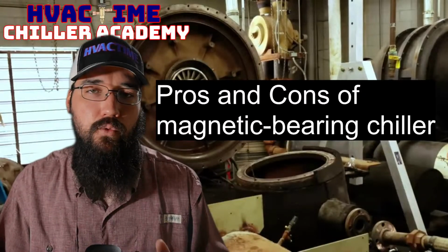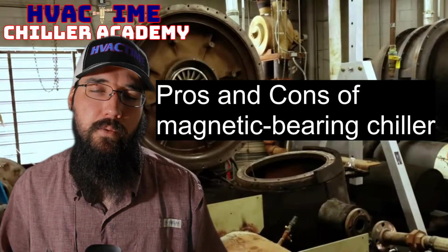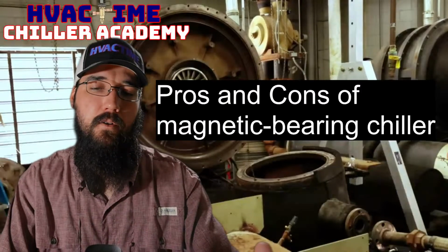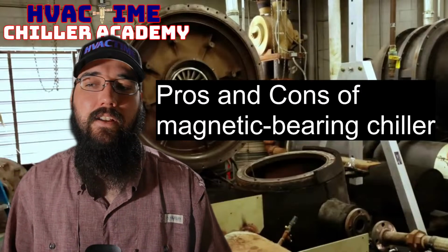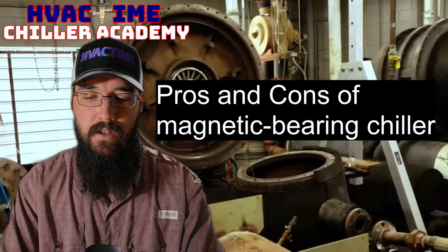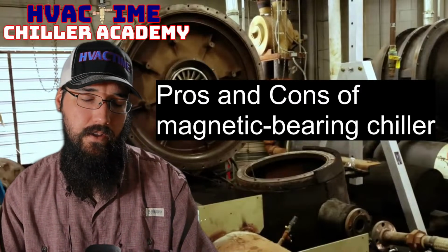That oil is just an insulator. We don't like it, it reduces our ability to transfer heat. So by removing that oil from the equation, our ability to transfer improves. Our approaches are able to maintain even lower values, which means we have even better efficiency in the end. I think those are the two major things.